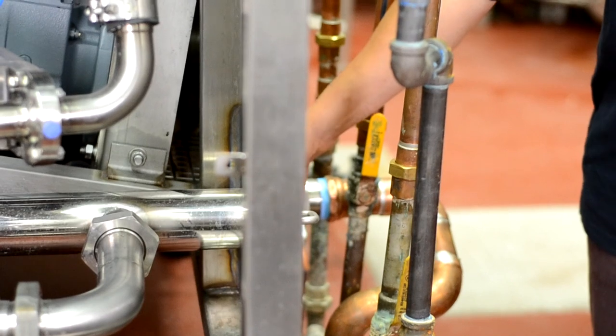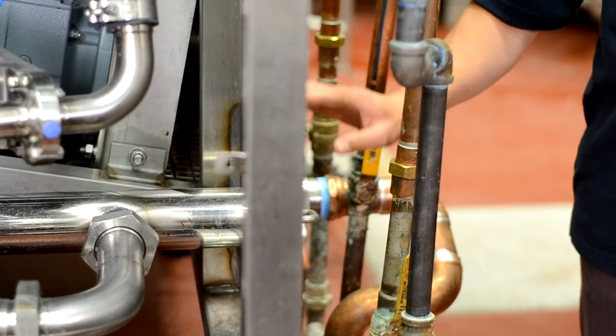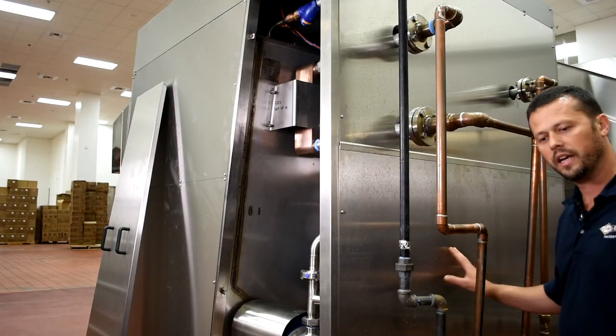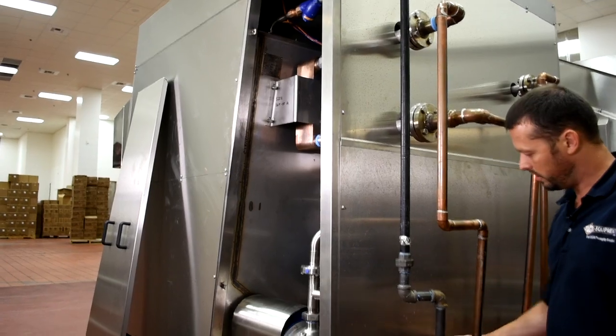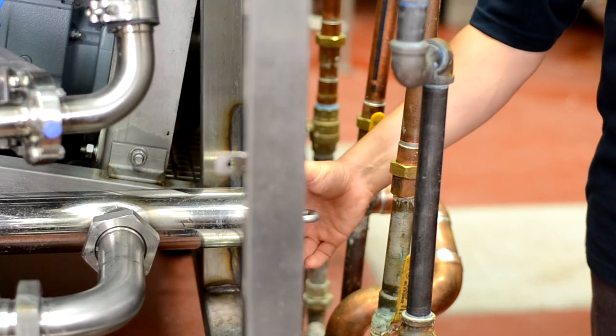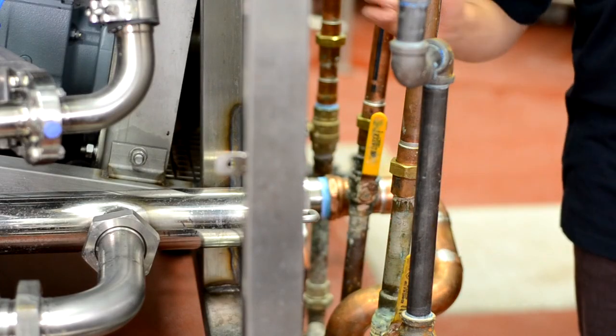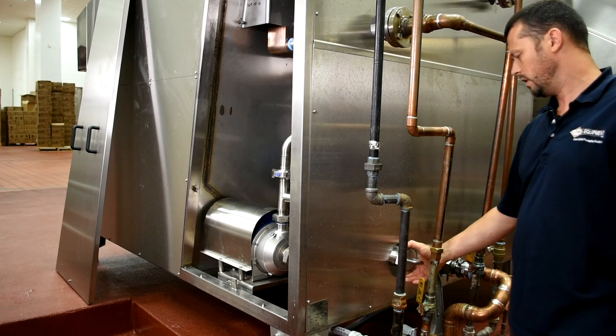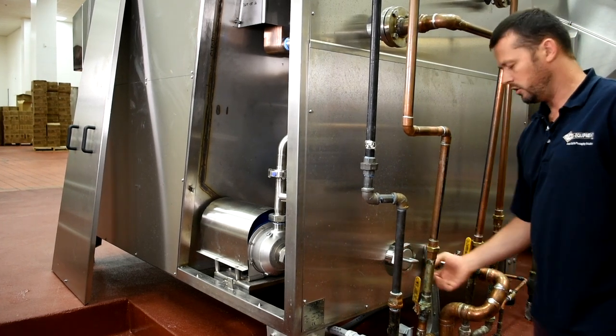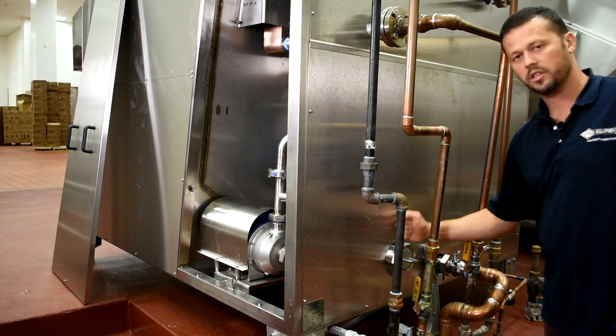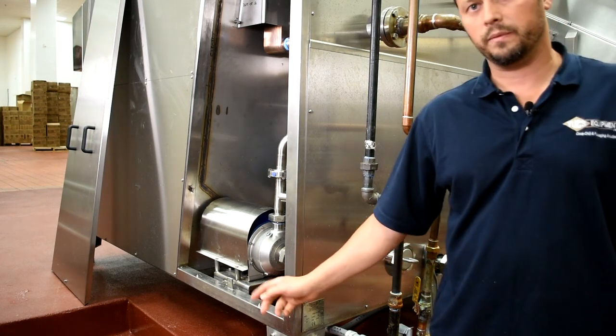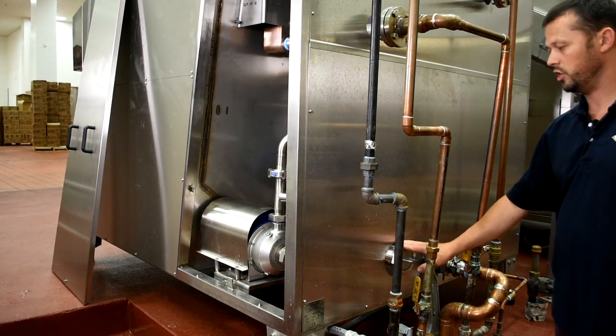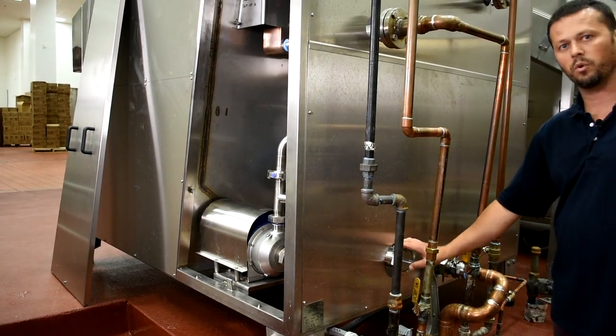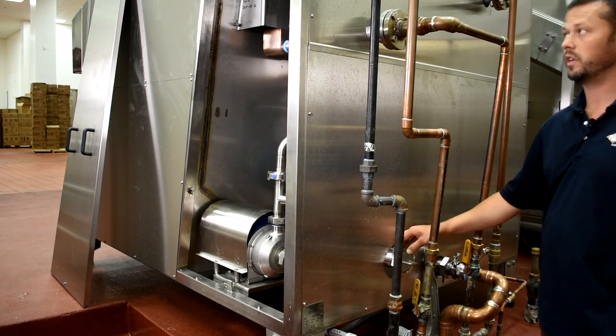If the operators notice that they are breaking the product inside, you need to shut the machine off, drain it, open this filter, remove it, clean it, and restart the process. You will probably have to clean the machine one more time and then check the filter. Because if the filter is clogged, it will burn out the pump. So it's very important to check the filter, especially if we know that the bags are broken inside the chill tank.